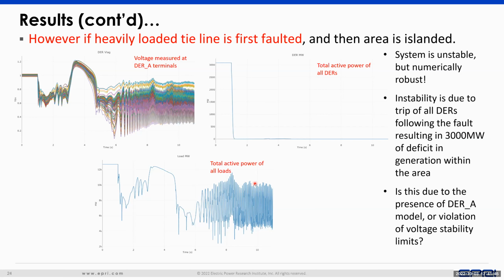So in this particular example, if you have 3 gigawatt of DER generation and you have a fault which causes the voltage to go quite low for an extended period of time, then all the DER trip and you have 3 gigawatt of loss of generation. And since the system is separating, you essentially do not have enough headroom or energy reserves to ride through that loss of generation, which then results in the entire simulation crashing.